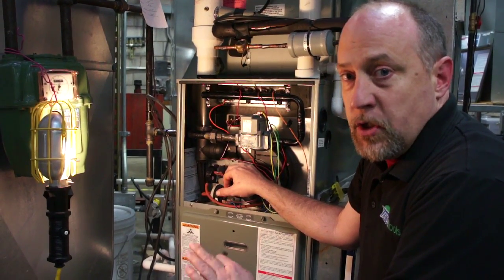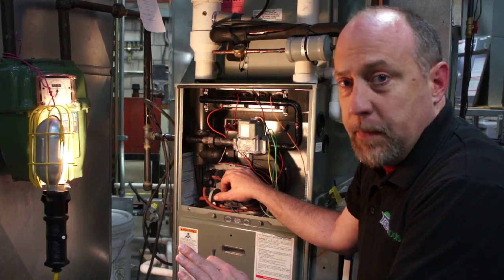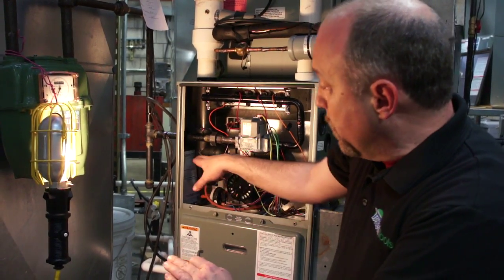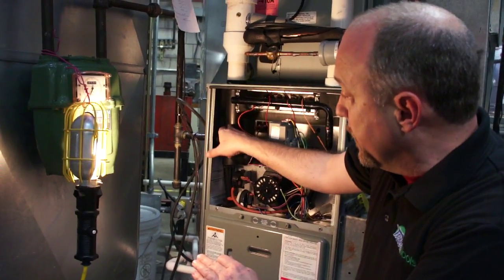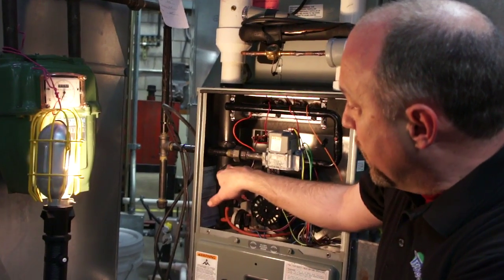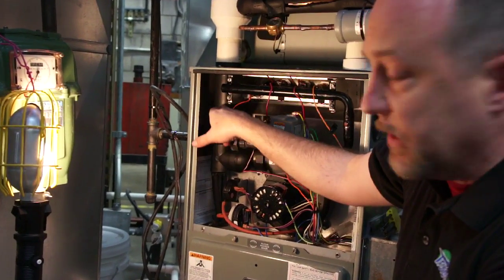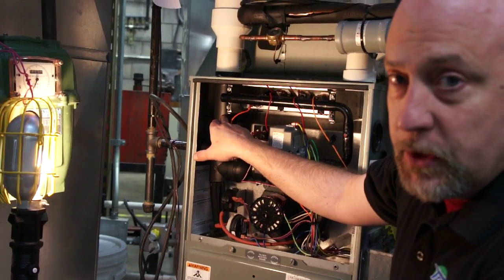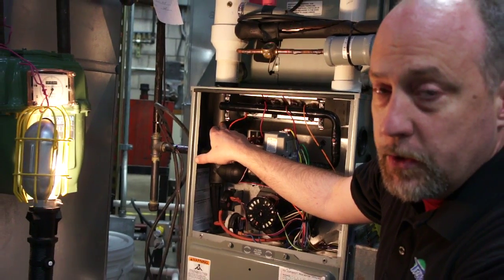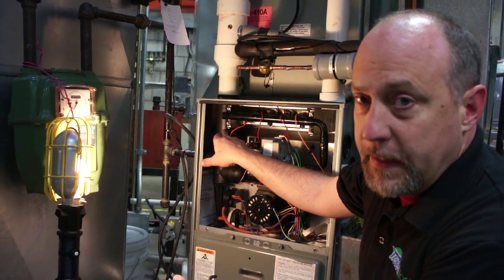So picking a hole location can be pretty important, and what you don't want to do is be too close to the draft inducer. We don't want to drill through this thin plastic, but also the velocity of the flue gases as they travel up here can cause problems with our static pressure reading in our stack when we go to do the draft reading on the analyzer.